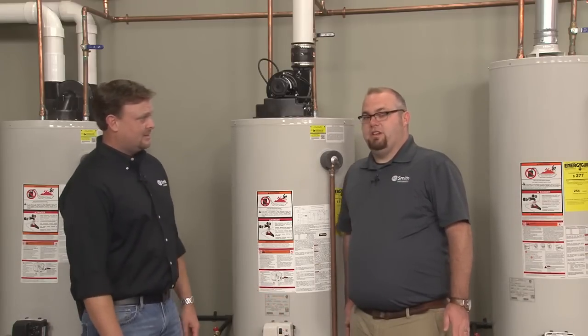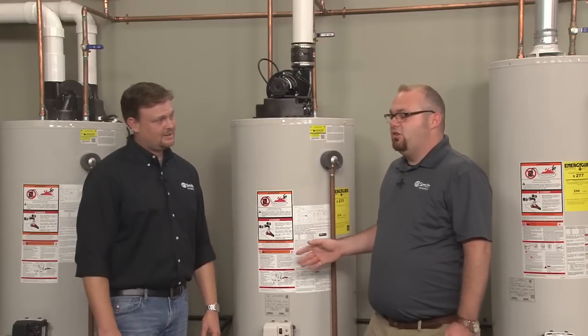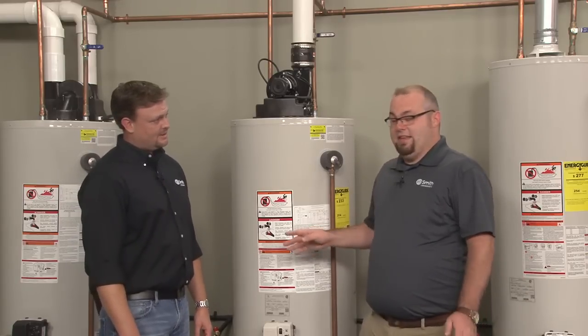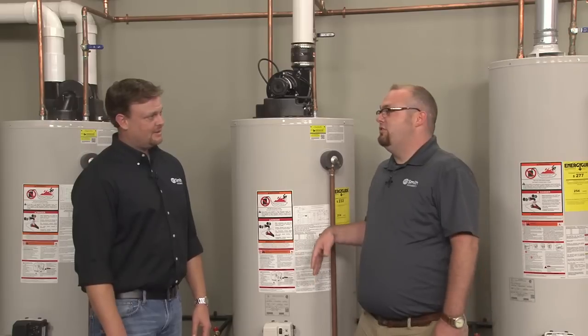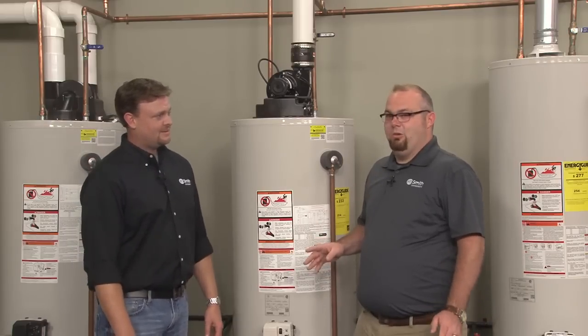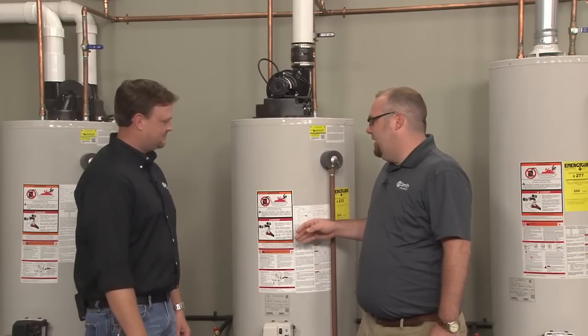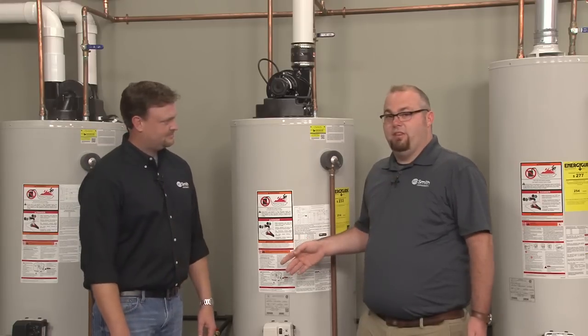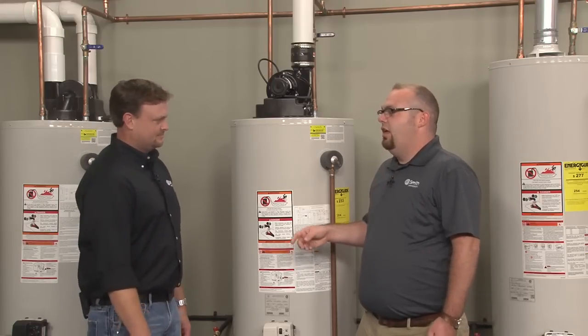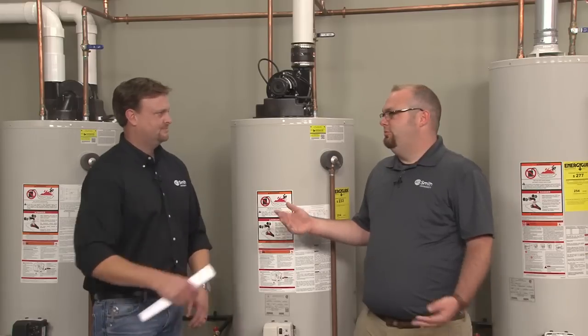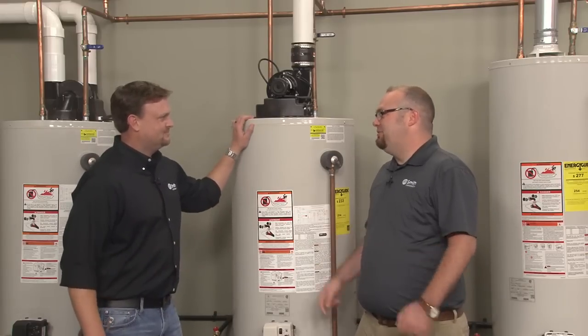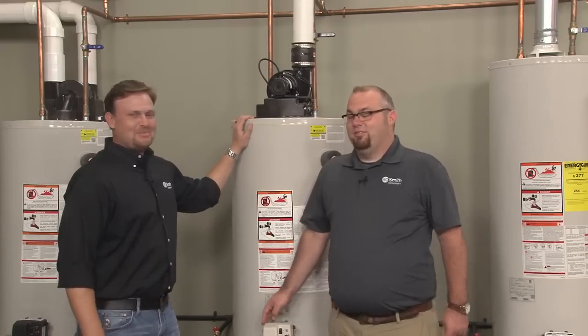There is a reset procedure. So say the heater locked out. First of all, you should not be doing anything with flammable vapors near the heater. Even though it's a flammable vapor design, you never want to test that sort of thing. It's just not recommended. So if you're going to do anything flammable around it, turn the heater off, or do the flammable activities somewhere else. Okay.